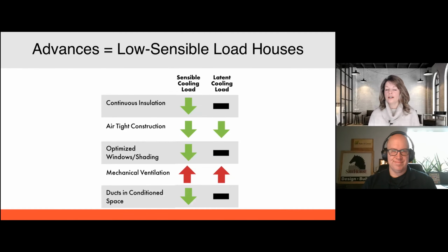So as we talked about before, advances in high performance homes or low load homes really are advances in low sensible load homes. It really isn't low latent load homes. It's that low sensible. So ACCA, the Air Conditioning Contractors of America, has a new manual out. They have Manual J, Manual S, Manual D. They have Manual LLH, which is low load homes, and it is a manual of recommendations for sizing and designing our HVAC systems in lower load homes. And in these lower load homes, we see continuous insulation driving down our sensible cooling loads, airtight construction, better windows.